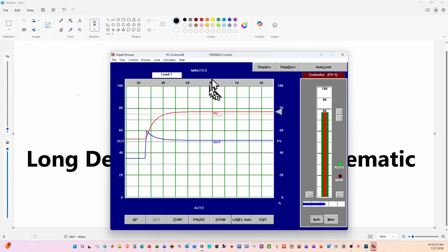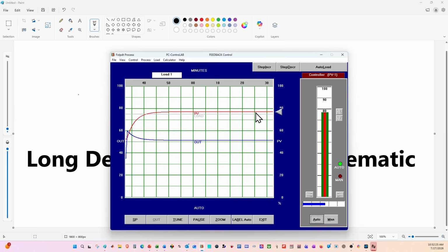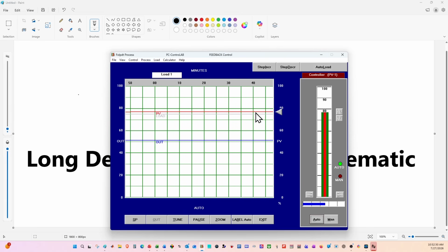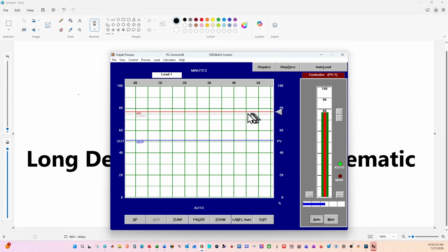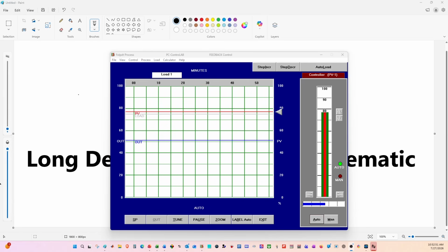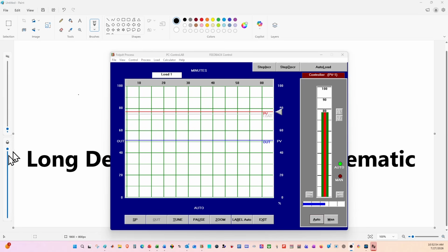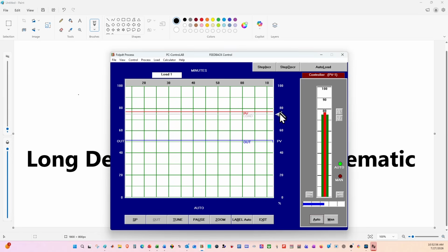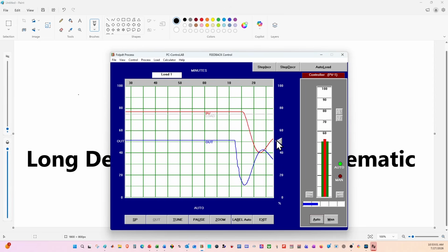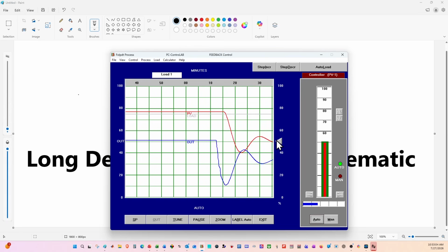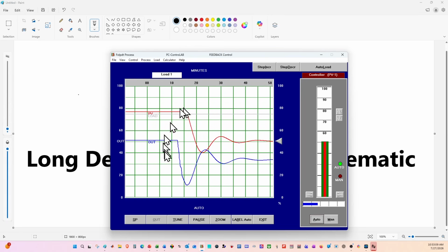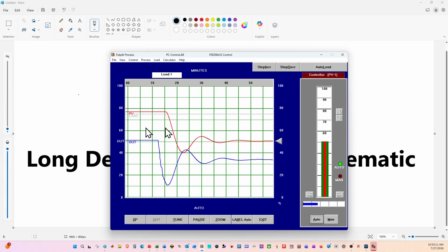Now, my time scale is in minutes. Again, from left to right, every green block is going to be 5 minutes. I'm therefore going to put in a time delay of 3 minutes. As I change the set point, you're going to see that the process variable will take 3 minutes before it responds. And that is going to have an influence on my process. Immediately, you can see that the process has slight oscillations because of the time delay. So it is not as crisp as it would have been.